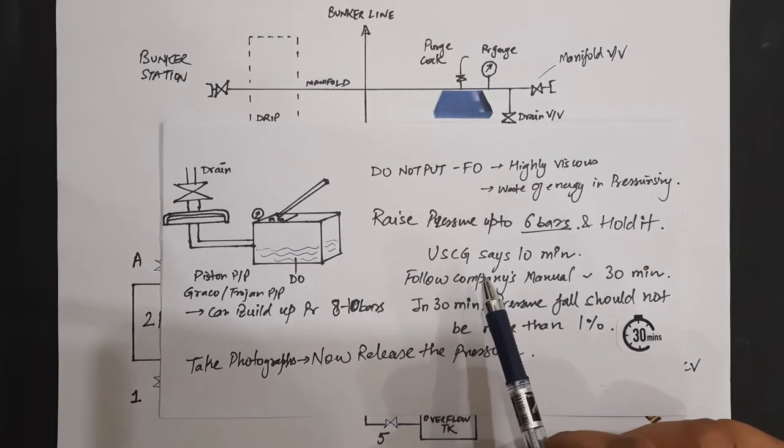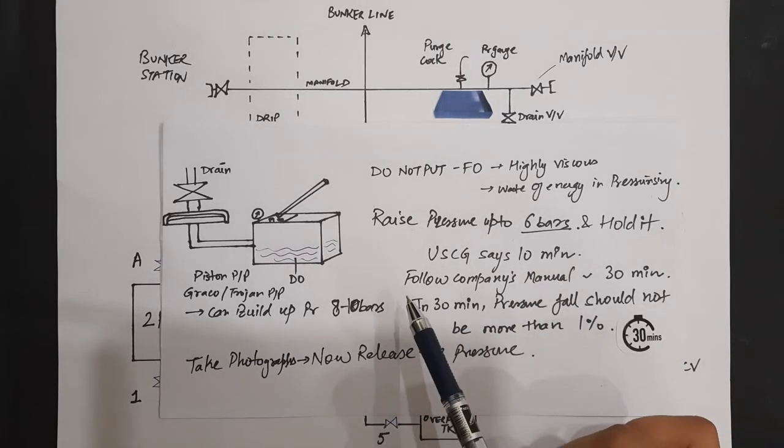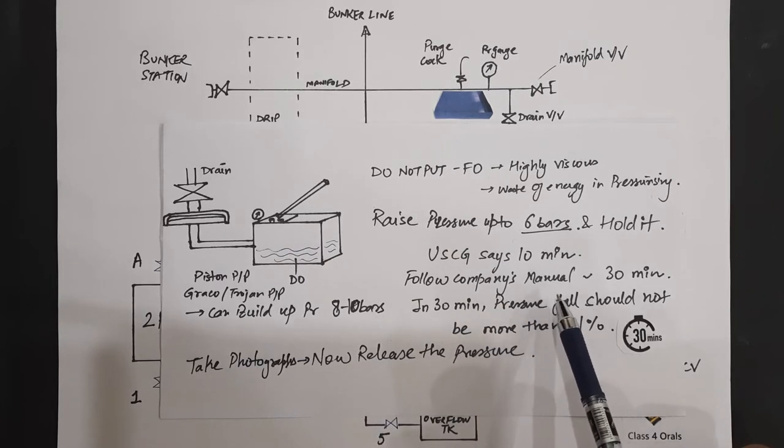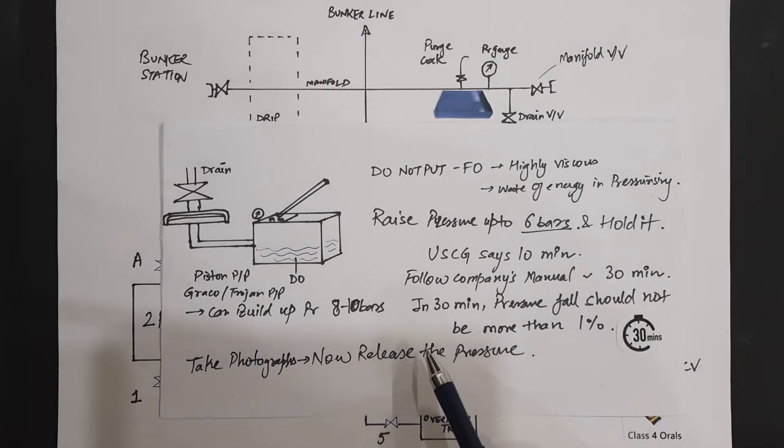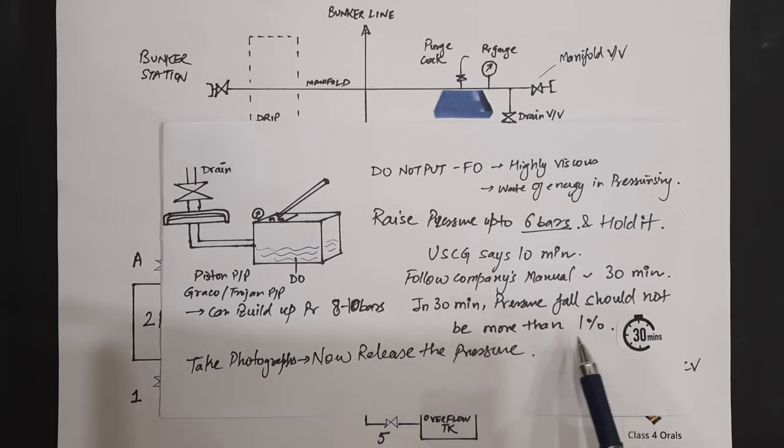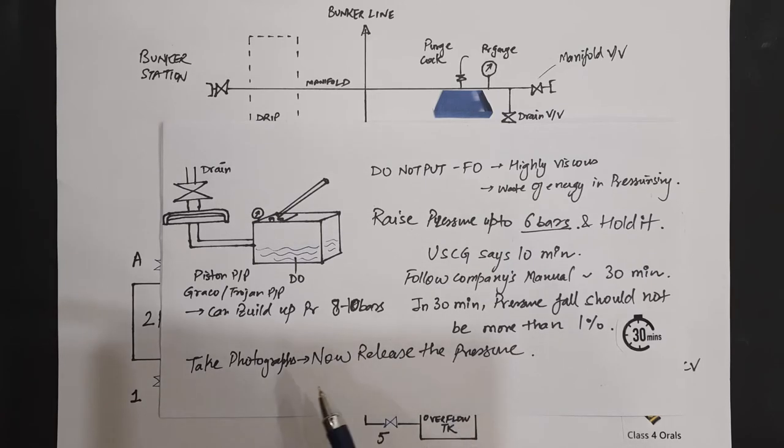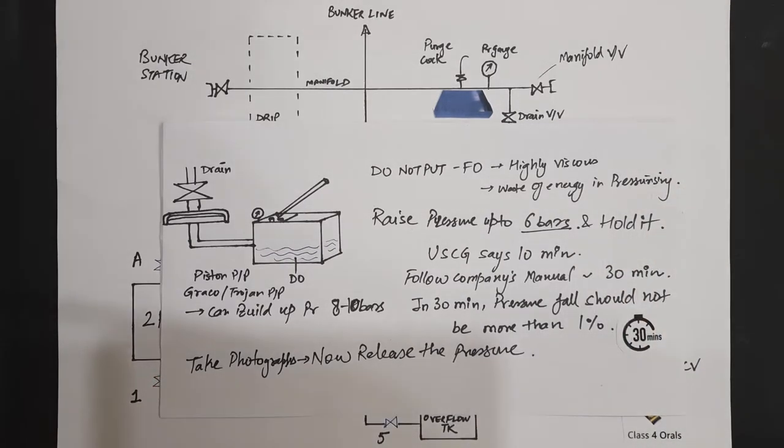Now, as per the USCG, it says it should be held for 10 minutes. But always follow the company's manual because it is more stringent. Suppose the company manual says 30 minutes. Then as per the thumb rule, in 30 minutes, the pressure should not fall more than 1%. And after that, after 30 minutes are over, take the photographs of the test being conducted with proper pressure gauge in the photograph. And now we are going to release the pressure.